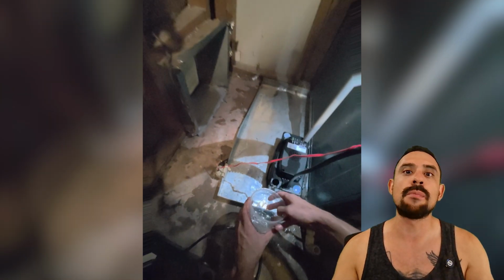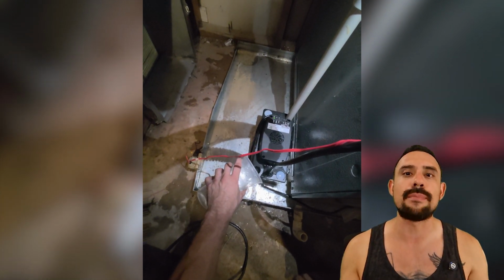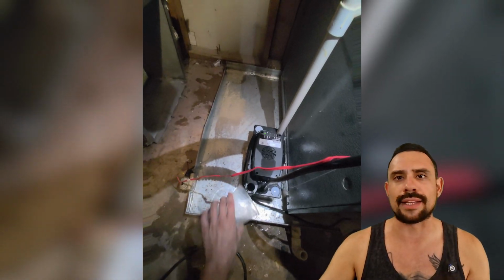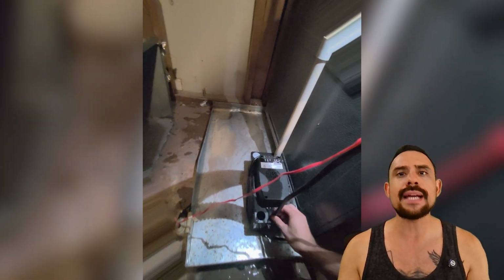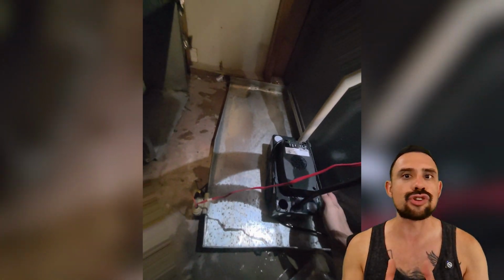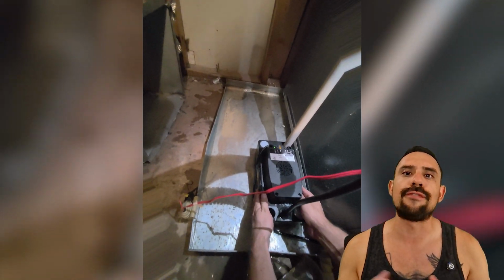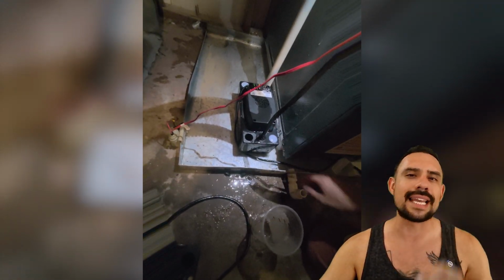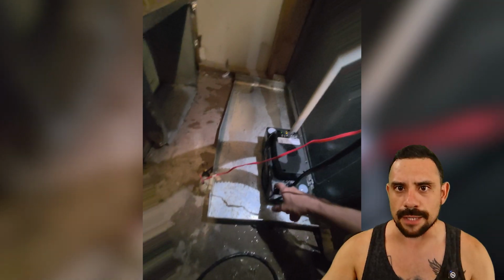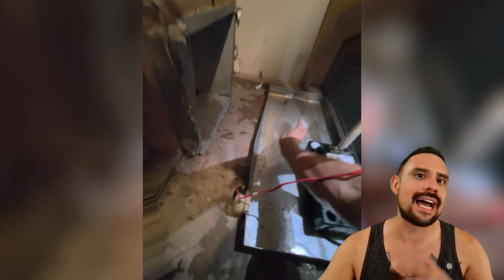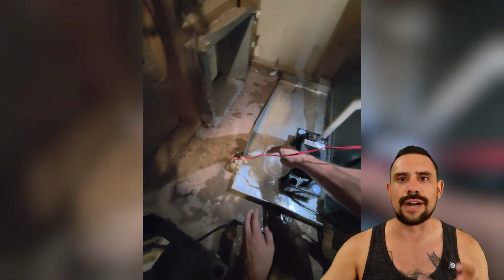Now I can take some of the water that's pooled in the safety pan and manually pour it directly into the open hole. It might take quite a bit of water to raise the internal float switch before it finally kicks in, but this is the exact sound you want to be hearing. The pump is now running and actively pushing water out.